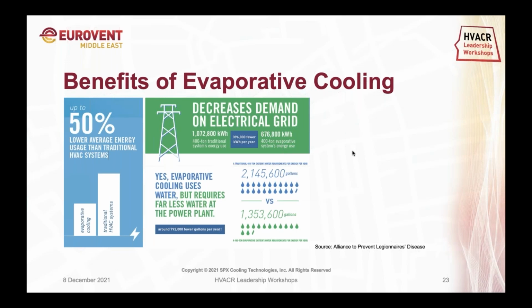And finally, again referring to power consumption: yes, on the site level, on the building level, the water-cooled system will consume water. But if you compare it to the water required to overcome the energy consumption generated by the air-cooled system, you'll find it's almost 30 to 40% less than what you'd consume at your building. This is an example of a 400-ton air-cooled versus water-cooled system: at the power grid, it requires 2.1 million gallons versus 1.3 million gallons per year. These data have been backed up by studies, and this article was sourced from the Alliance of Legionnaire.